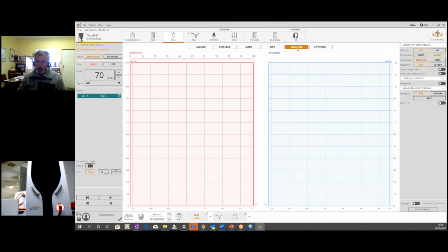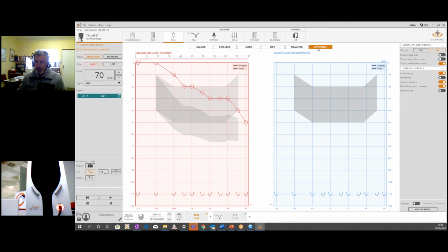Advanced setting, as I told you before, allows you to have a more focused vision of what is happening, because the frequency range is higher, up to 12 kilohertz. And in my opinion, one of the most important features we have implemented is the live speech. Because the live speech module is a counseling tool. The patient wears the hearing aid, turned on, and at the same time you can acquire a couple of curves: how the patient can hear the sound with the hearing aid, and how the patient can hear the sound without the hearing aid.